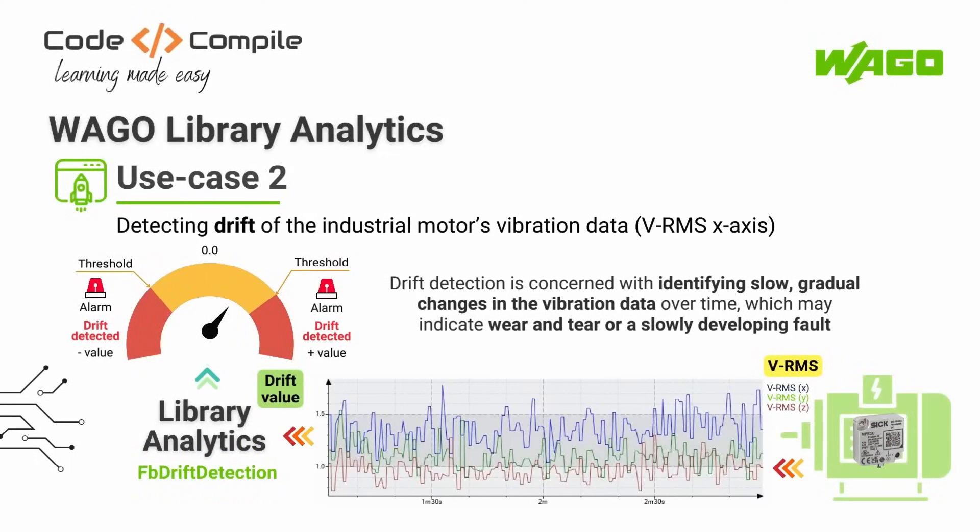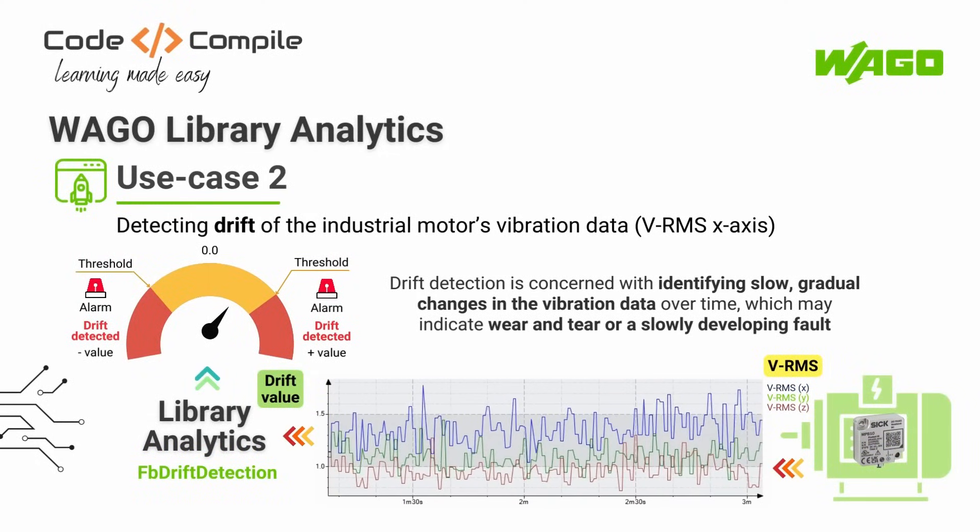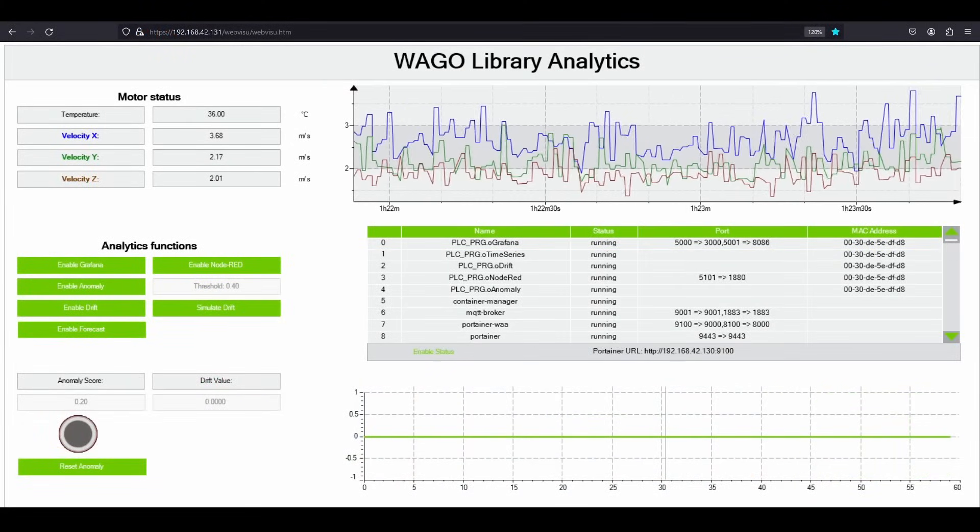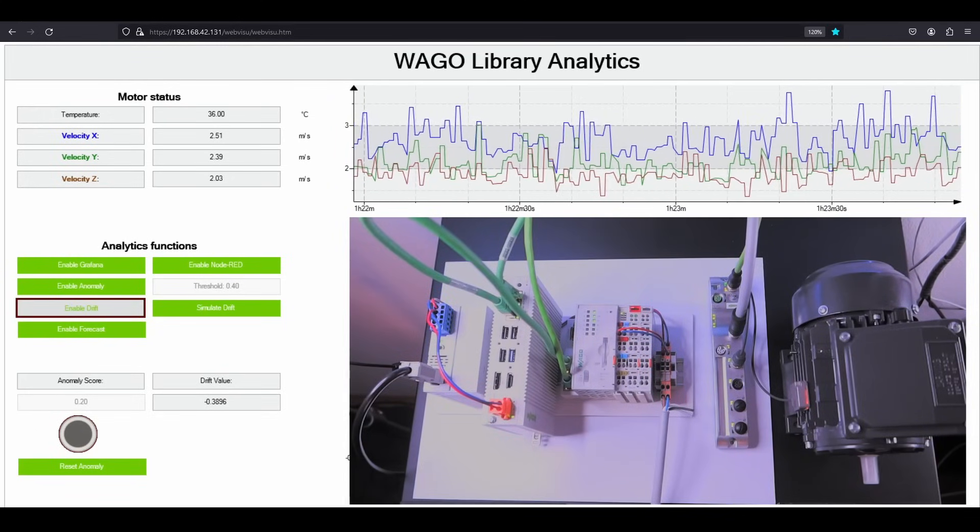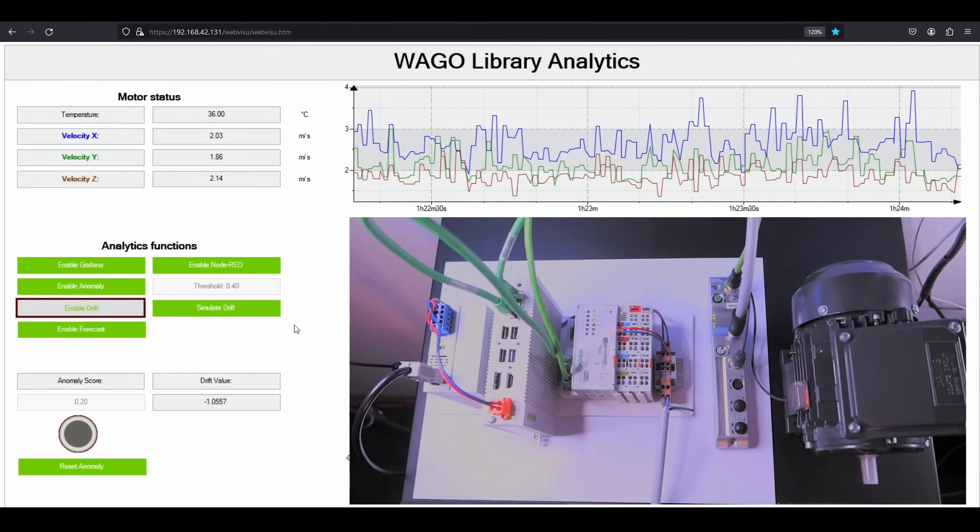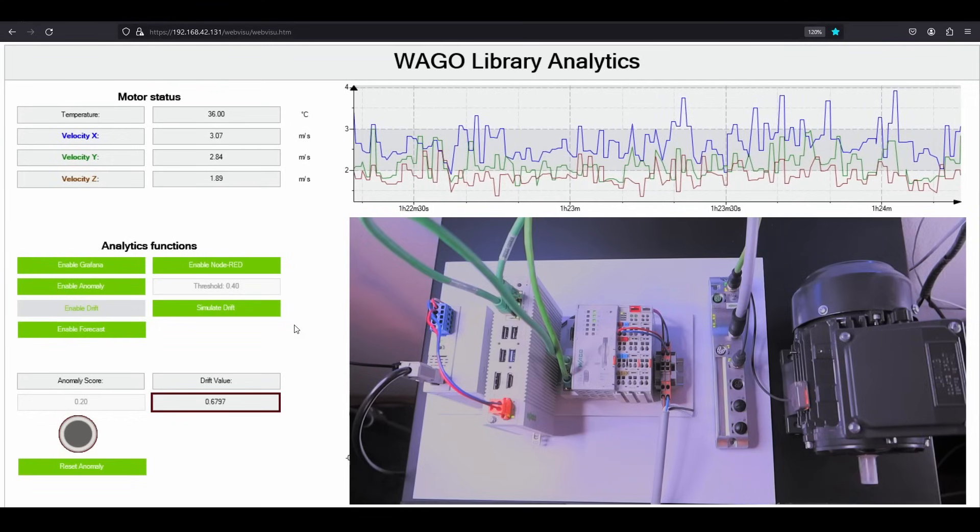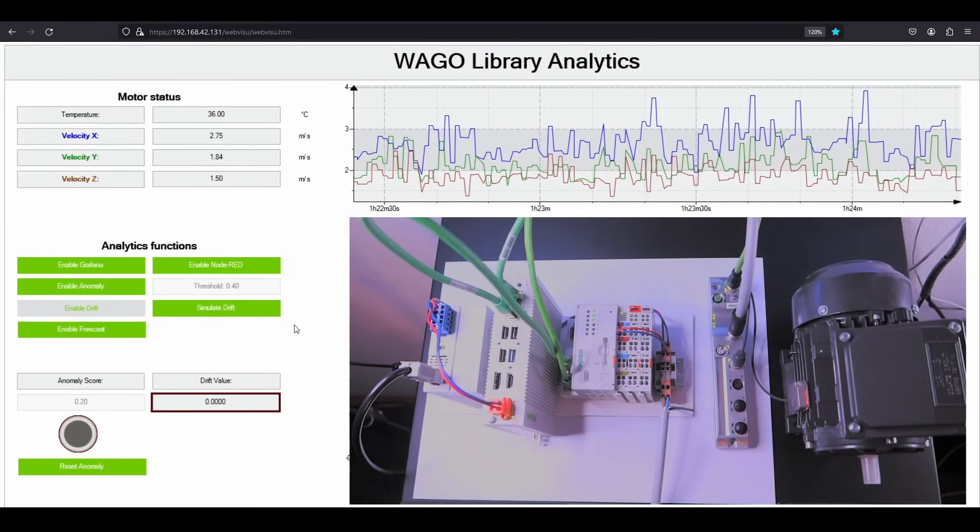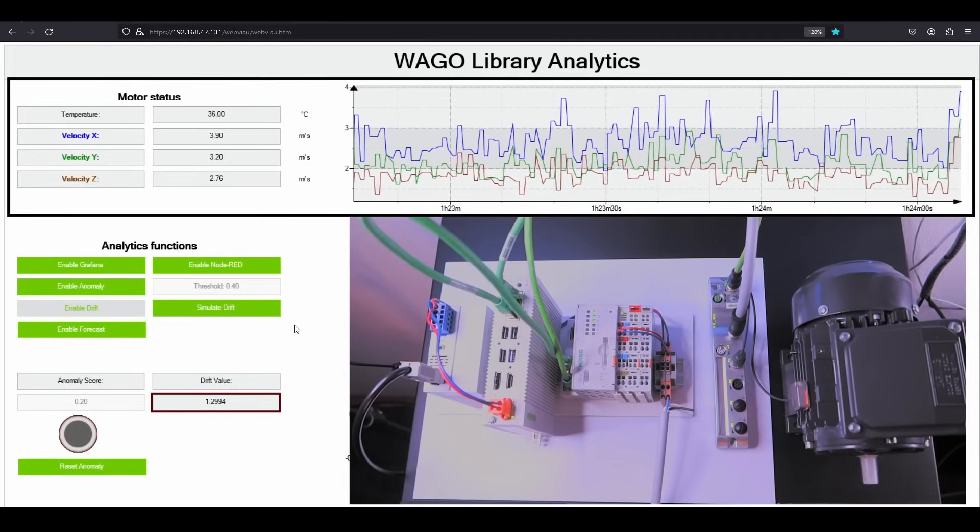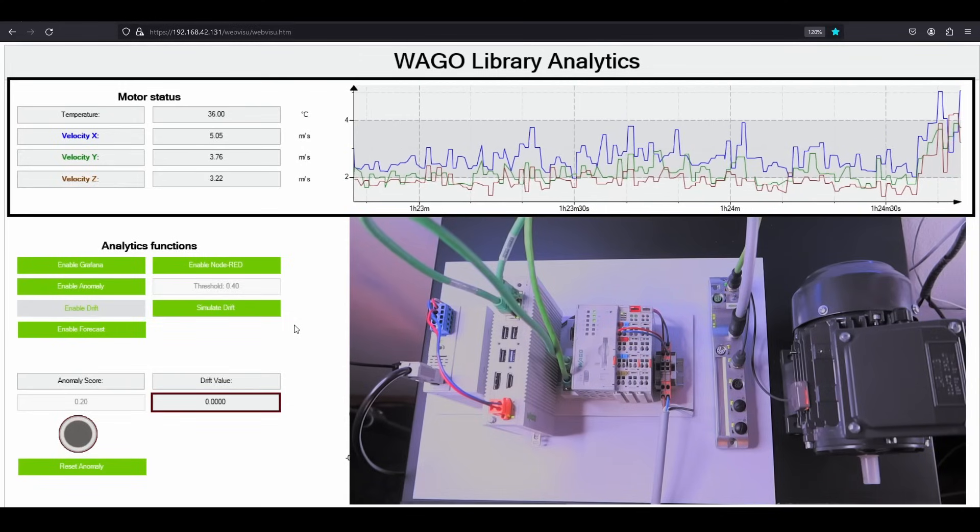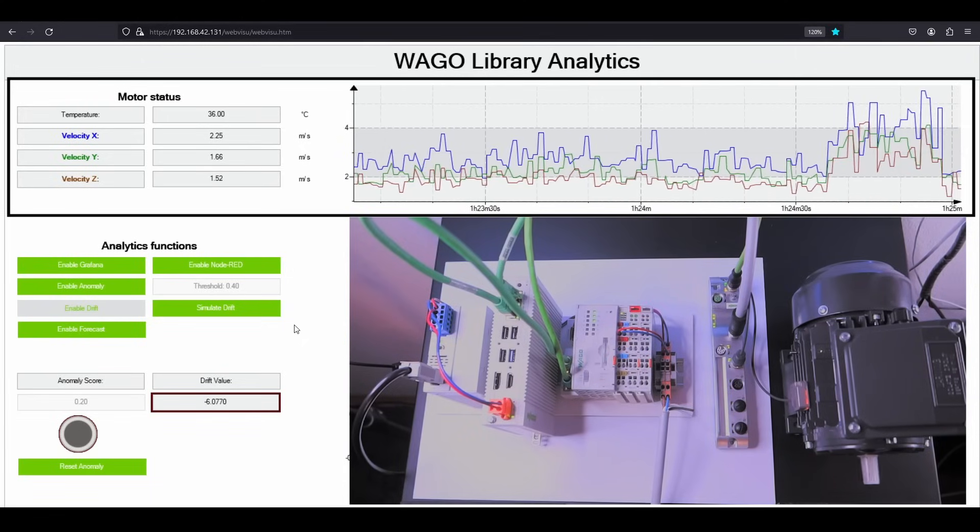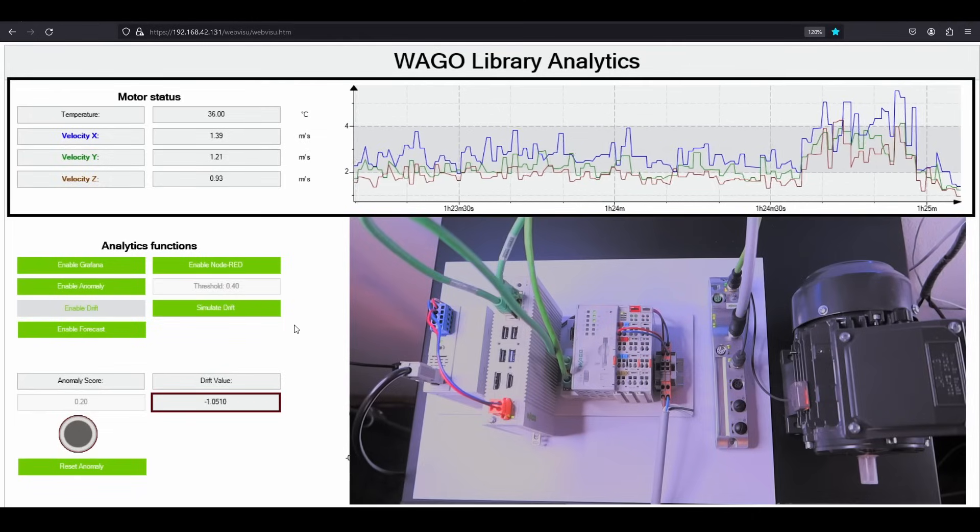Now we will detect the drift of the motor, which indicates a slow and gradual change in the motor's vibrations over time. This could be an indication of wear and tear or slowly developing faults. Let's enable the drift detection from this button and it will start sending motor vibration values to the Docker container responsible for calculating the drift value. At the moment, the drift value is close to zero. Let me introduce some gradual changes in the motor vibration by increasing the motor speed via the variable frequency drive, which is hidden underneath the motor. You can see that with the increase in the motor speed, the vibrations are increasing, and hence the drift value. And with the decrease in motor speed, the vibrations are decreasing, and also the drift value.